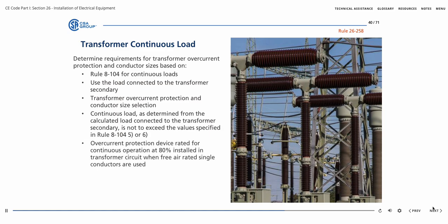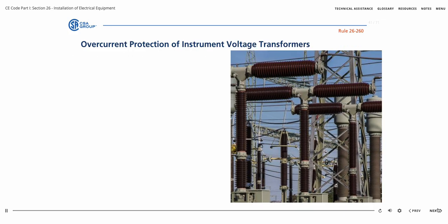When an overcurrent protection device rated for continuous operation at 80% is installed in the transformer circuit, when free air rated single conductors are being used, a derating of 70% is used to determine the amount of continuous plus non-continuous loads that can be connected to the overcurrent device.